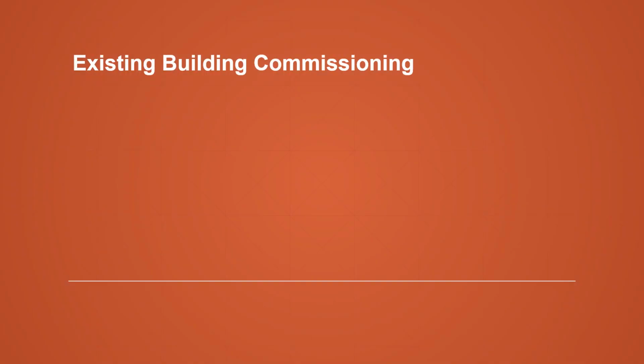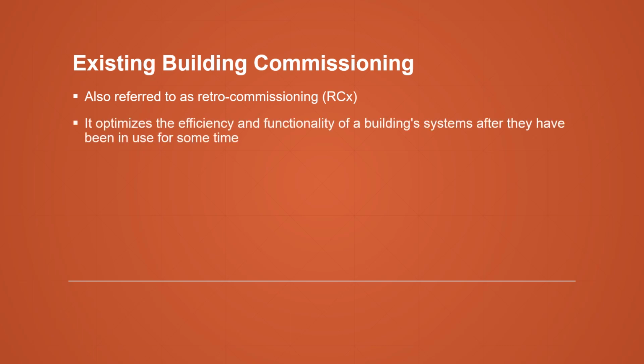Commissioning does not only apply to newly constructed buildings. Commissioning can be used with existing buildings as well. Existing building commissioning, also known as retro-commissioning, is a process that involves reviewing and improving the performance of existing building systems. It is an effective means of improving the efficiency and functionality of a building's systems after they've been in use for some time. In the LEED Existing Buildings Rating System, several credits are available associated with the implementation of existing building commissioning.